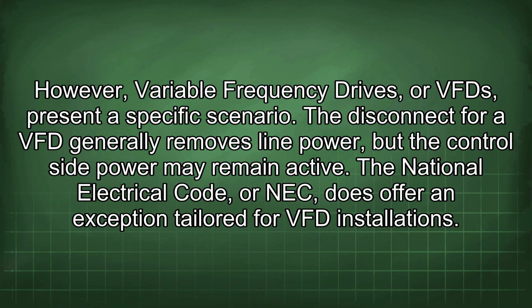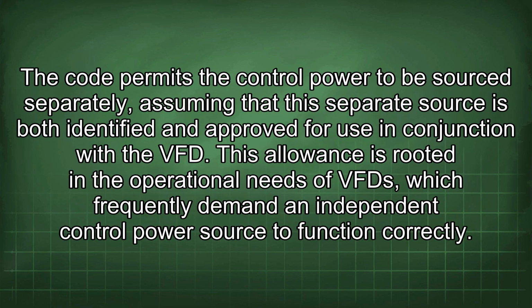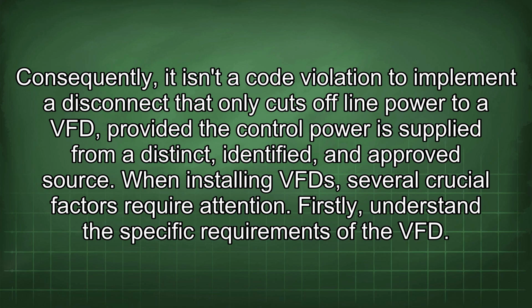The National Electrical Code, or NEC, does offer an exception tailored for VFD installations. The code permits the control power to be sourced separately, assuming that this separate source is both identified and approved for use in conjunction with the VFD. This allowance is rooted in the operational needs of VFDs, which frequently demand an independent control power source to function correctly. Consequently, it isn't a code violation to implement a disconnect that only cuts off line power to a VFD, provided the control power is supplied from a distinct, identified, and approved source.